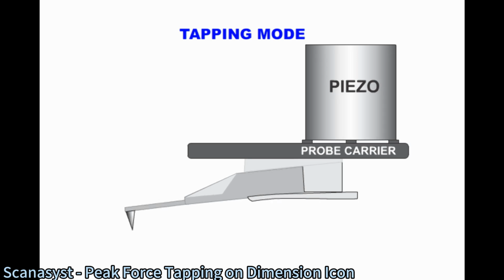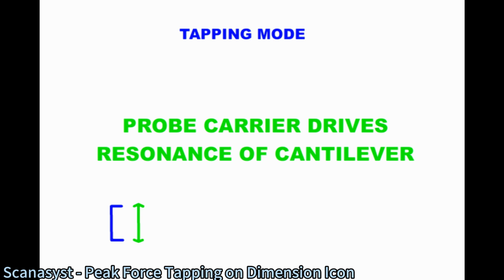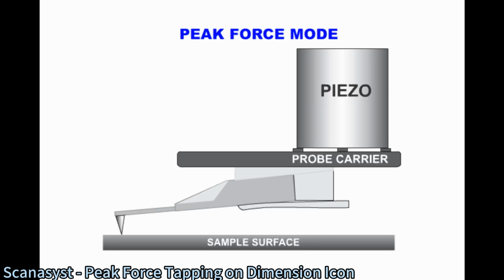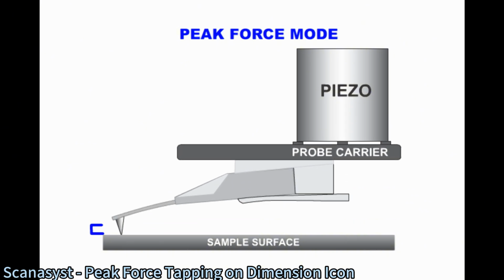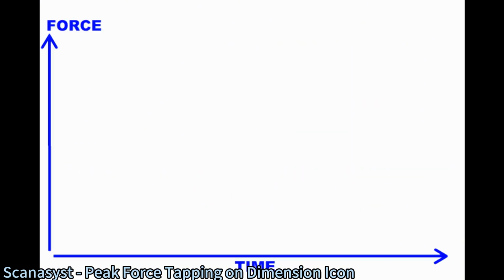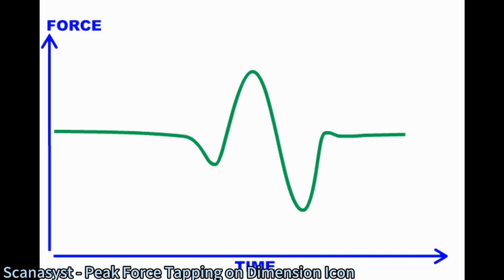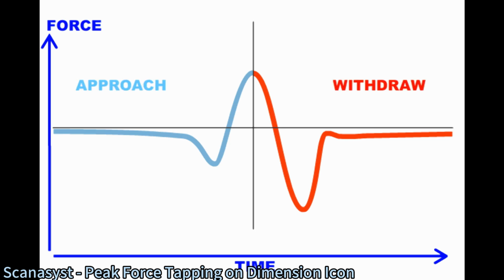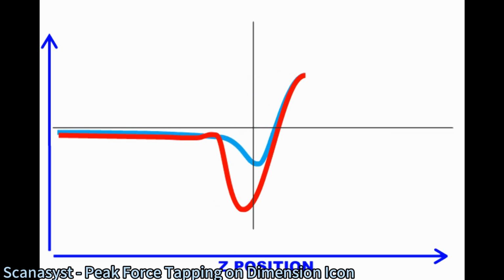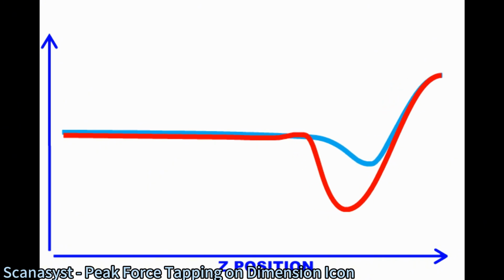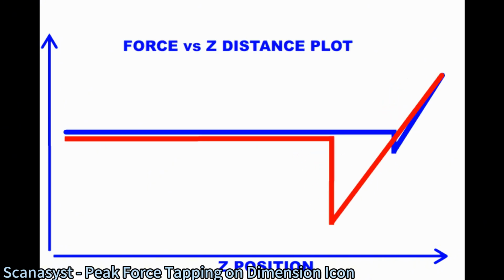Standard tapping mode imaging involves the monitoring of a probe cantilever that is vibrating at its maximum resonance frequency. Peak force tapping involves driving the probe with the scanner's piezo at a frequency much lower than the resonance value of the cantilever. Using a nonlinear cyclic ramp, the scanner piezo moves the tip and sample together and apart within a small range of vertical amplitude. This cycle results in a force data plot over time that can be divided into approach and withdrawal segments that, when plotted as force versus Z position, will take on the familiar appearance of a force ramp plot.